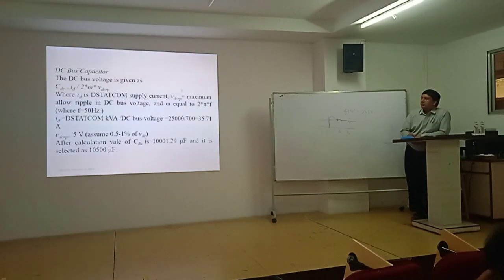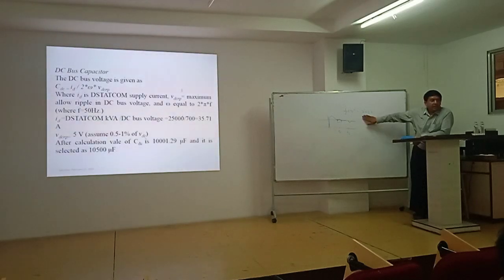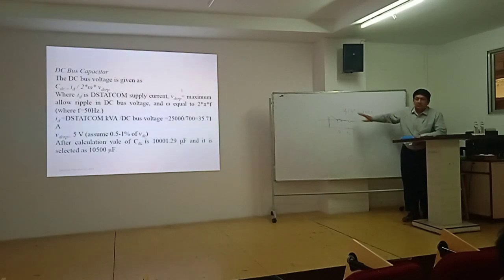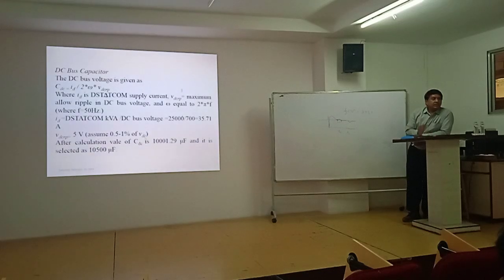This formula is used on the DC side, as you can check. In a converter we have AC and DC. So this formula is based on the energy balance, based on the DC side calculation. CDC equals ID divided by 2 omega times the ripple component on the DC bus.